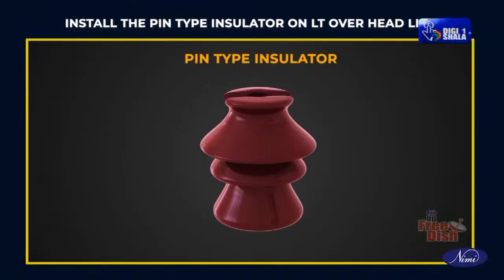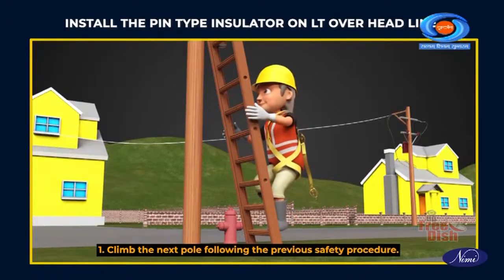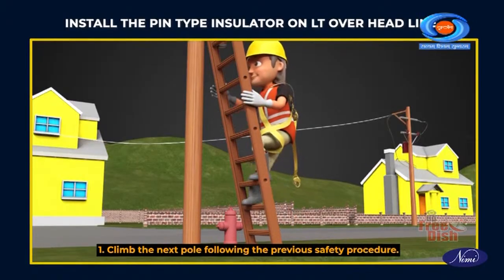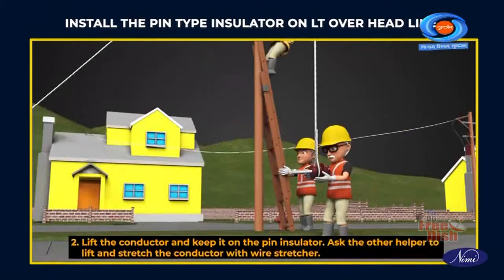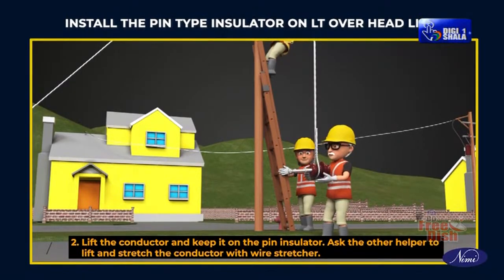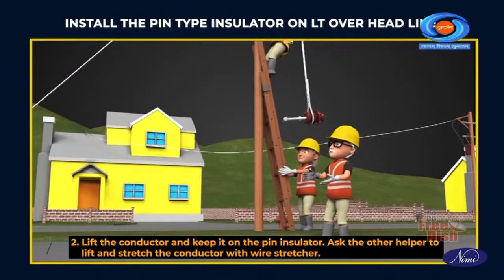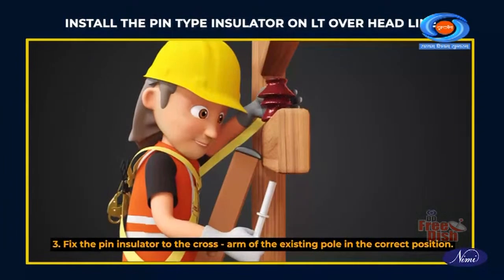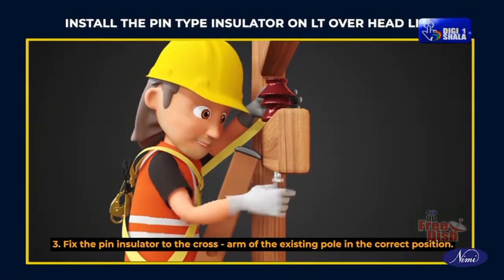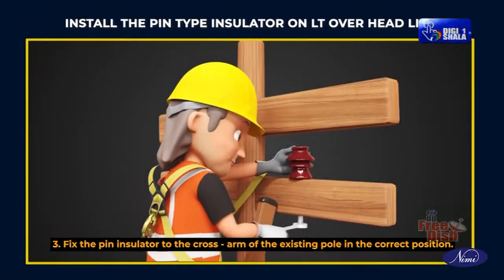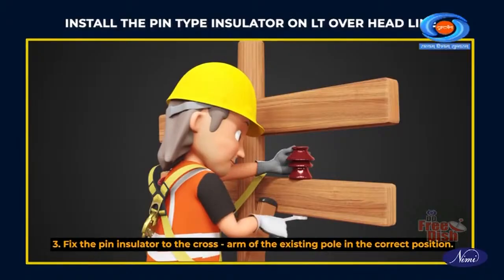Install the pin type insulator on LT overhead line. Climb the next pole following the previous safety procedure. Lift the conductor and keep it on the pin insulator. Ask the other helper to lift and stretch the conductor with wire stretcher. Fix the pin insulator to the cross arm of the existing pole in the correct position.